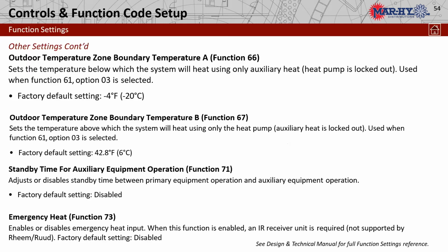And 66, that's zone boundary temperature A. This one you will leave set to 00. This is to lock out the heat pump. Now, I've always advocated there's no reason to ever lock out the heat pump. Even in the worst case scenario, it makes more heat than strip heat for the money.